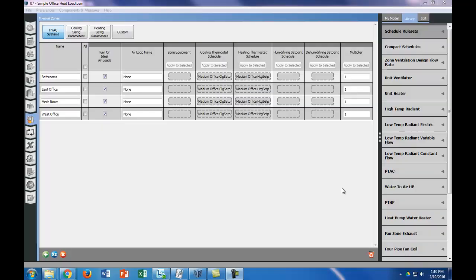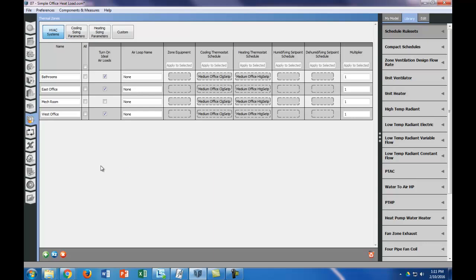We're almost ready to run our model, but we need to make a few more tweaks just to make sure that our model is following our assumptions. So the first thing we're going to do is get rid of this turn-on ideal air loads for the mechanical room. All the ideal air loads means is it's actually going to calculate the heating and cooling need for the spaces in an ideal, without any HVAC system, just an ideal model. So the mechanical room isn't conditioned, so that's why we're going to turn that off.